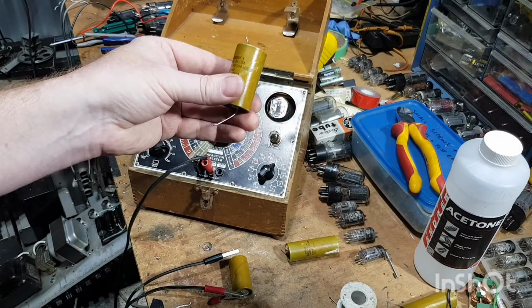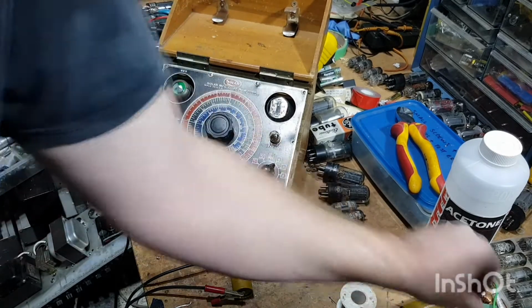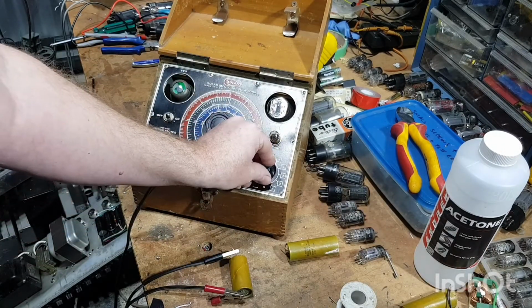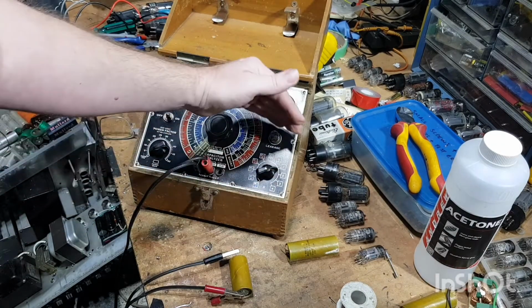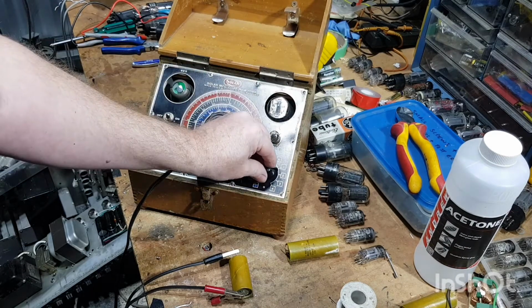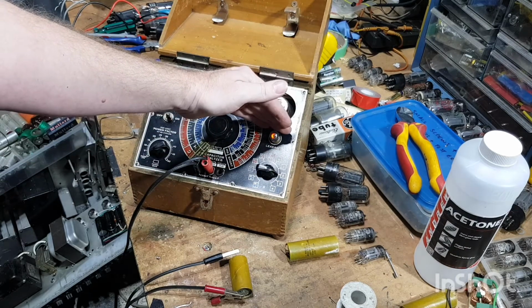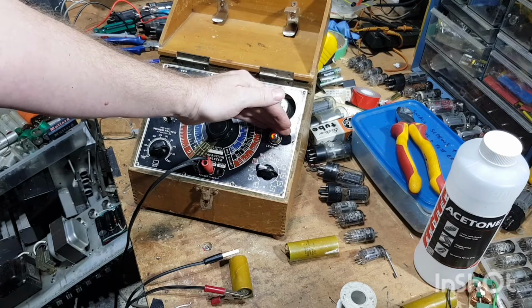I'll just check the voltage rating. I'm pretty sure it's a 350 volt. Oh no, these are 500 volts. Okay, so we can wind this thing up to the top to check for leakage. First position, okay. Second, about 250 volts or so, thereabouts. And it's leaking quite significantly.